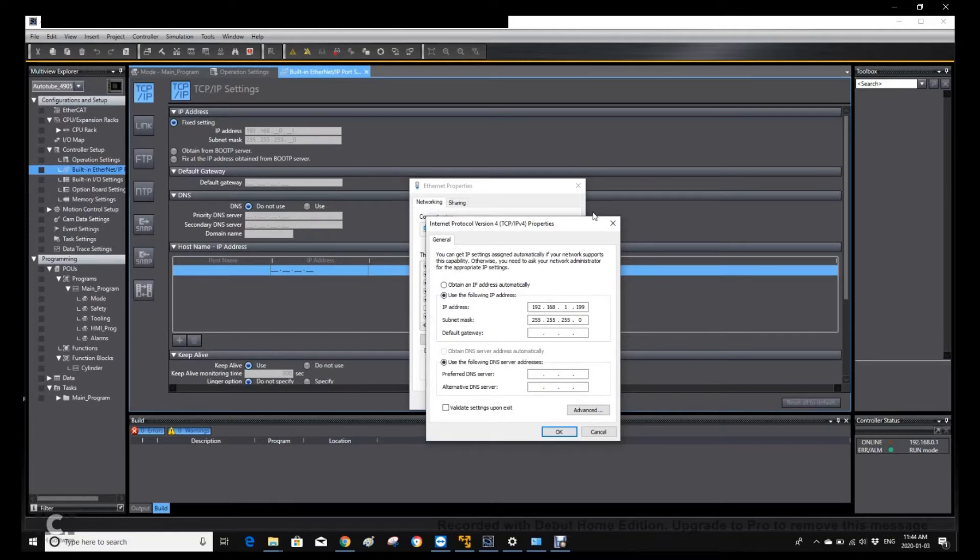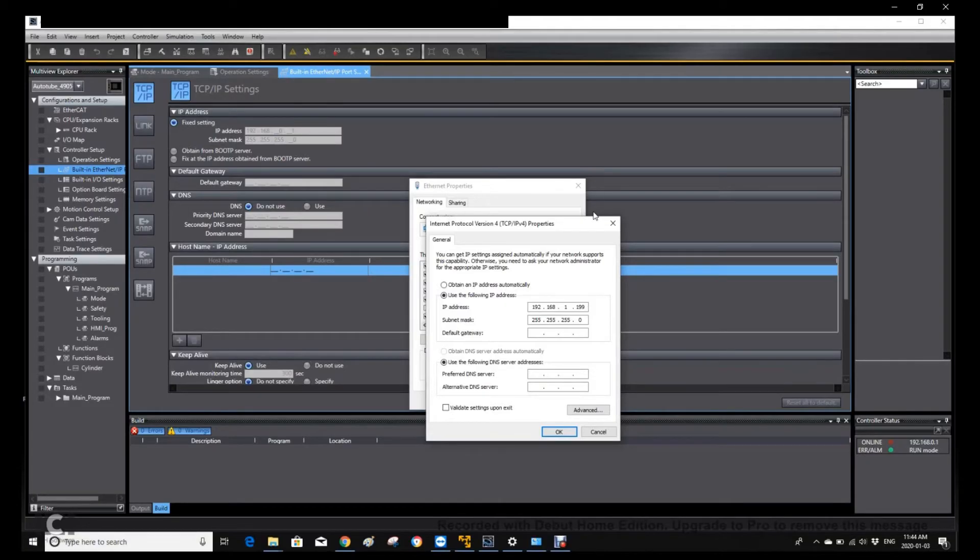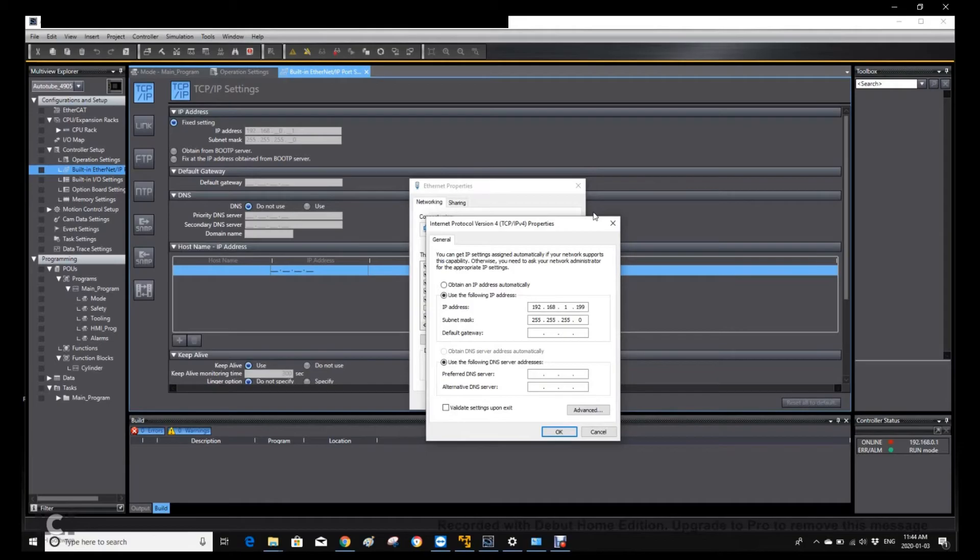After we connect this PLC, we can figure out the actual IP address of this controller. And after this, we can change our laptop IP address and the subnet mask. Or we can configure the IP address and download the hardware to this controller. So that we can override this new IP address to this PLC.